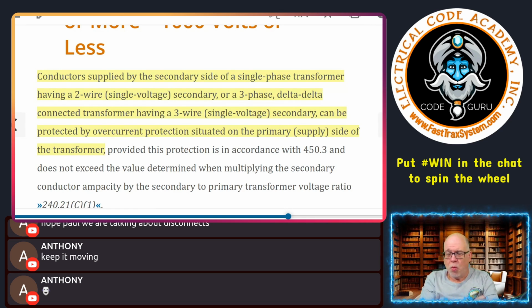Then if it's coming out with a 240, it's delta delta. So we'll go 480 primary and 240 secondary, and that's it. Not a 240/120. It's a three phase delta delta. It's just one single voltage coming in, one single voltage going out. Then there is a situation, and we have to do the math, where the primary protection of the transformer can also protect the secondary. So that's an application specific to one single voltage on the primary and the secondary.